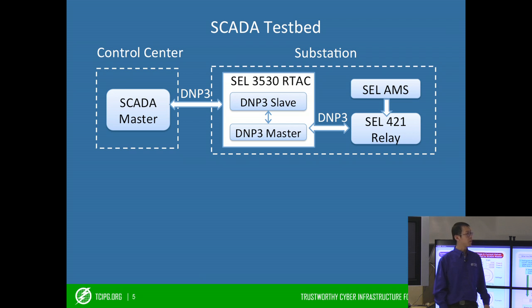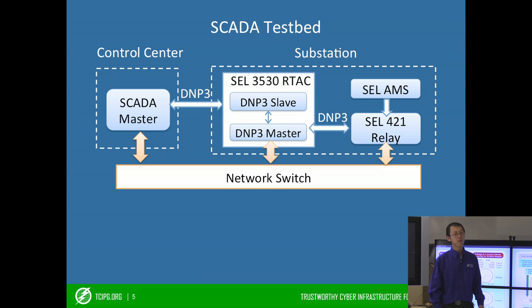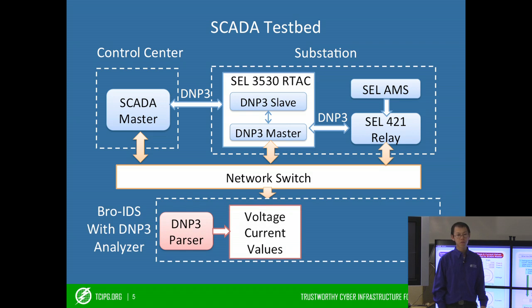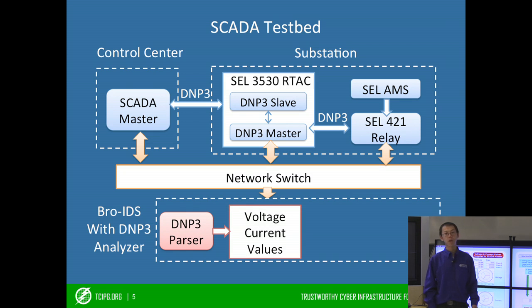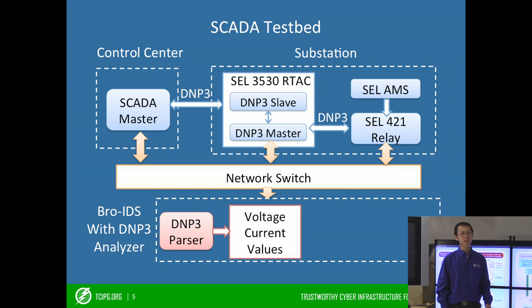Both of these communications are performed independently. In error-free operation, the measurement data carried by these two communications should be consistent with each other. In this lab configuration, we connect the SCADA master, RTAC, and relay into a network switch. We deployed our Bro IDS with the DNP3 analyzer on a separate laptop, and we connect this laptop to the network switch so we can monitor the traffic transmitted on both of these communications.